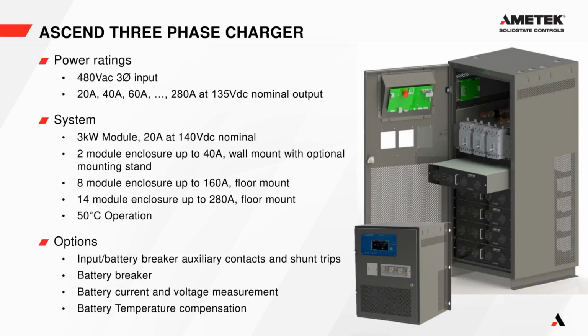Some of the options that we offer are auxiliary contacts for the input breaker and the battery breaker, and also shunt trips for those 2 breakers so that we can disconnect our charger when the battery is discharging or at the end of discharge, or if the charger runs away with the DC voltage, to shut off the AC input. We also offer a battery breaker option, so you can connect to the DC bus through our system and separately to a battery.